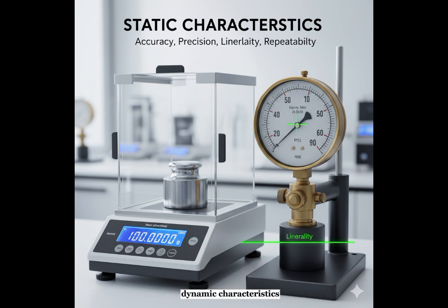Dynamic characteristics. Dynamic characteristics, on the other hand, describe how an instrument behaves when the input changes with time. Key terms include speed of response, how quickly the instrument reacts to a change; fidelity, how accurately the output follows rapid changes in the input; lag, the delay between input and output; dynamic error, the difference between the true input and the output when conditions change.